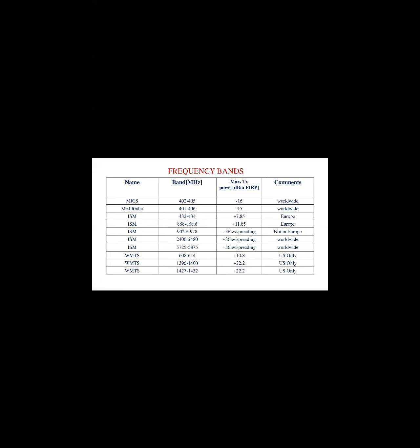This MICS band, which is used in the frequency range of 402 to 405 MHz, can have a maximum transmitted power of minus 16 dBm, which is accessed worldwide by the MICS band. These are all the frequency bands used for implantable applications recently. So the medical radio communication frequency is used for 401 to 406 MHz. They have a maximum transmitted power of minus 15. It is also a worldwide accessible frequency.